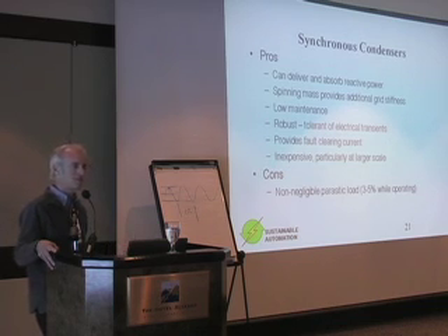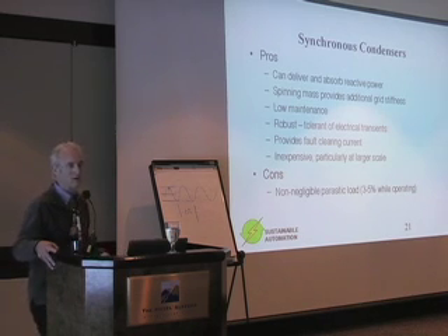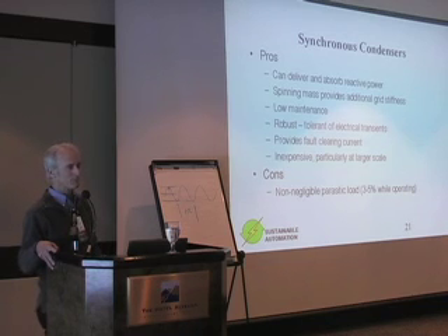One issue with synchronous condensers is that, because they are physical machines, they have bearings and friction, both mechanical friction and windage. There are some losses associated with operating them. Fortunately, you don't have to operate them all the time, only when you have wind power. Generally, you're not using diesel power to run the synchronous condenser, because you would only run it when you have a significant amount of wind power that you need to provide additional system stabilization for.